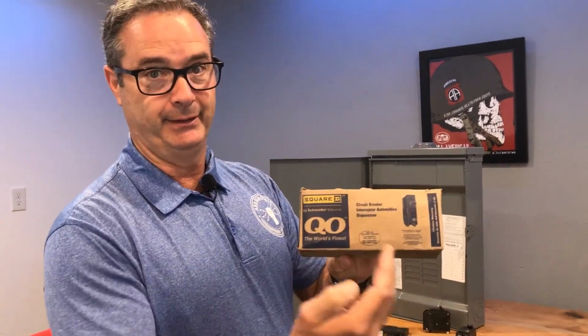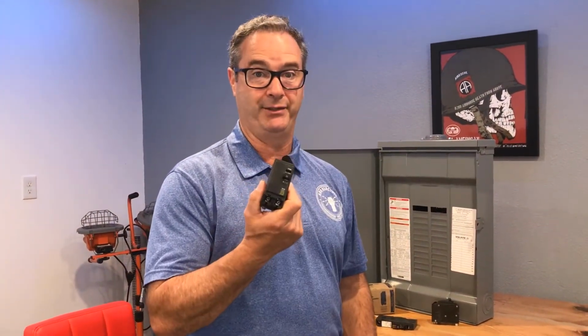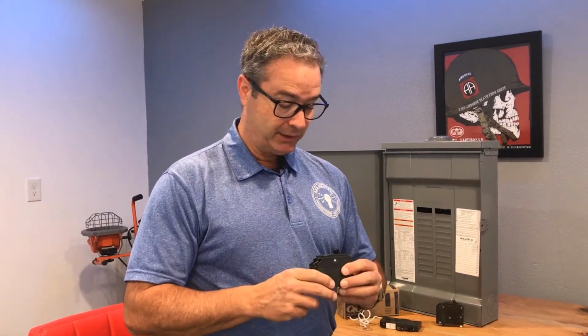Look at that. I love that. QO. Two letters. I'm not stymied by that. I can handle that. So why do I recommend it so highly? Lifetime warranty. Lifetime warranty on the panel, lifetime warranty on the breakers. So in thinking back since the early 90s, in terms of a bad breaker, I may have replaced maybe one or two over the course of almost 30 years. In those other panels, lots of other brands that you'll see out there, I've replaced dozens and dozens of those.